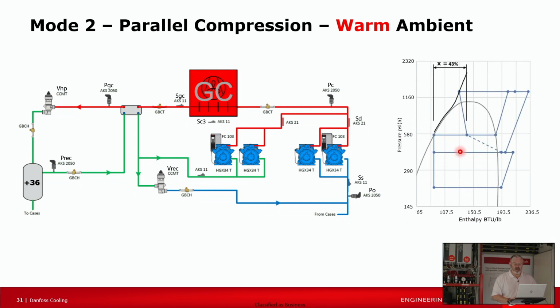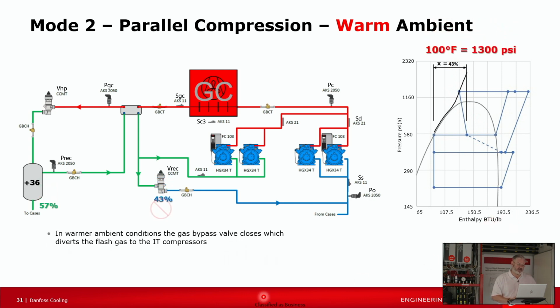So in a warm ambient, we've got 43% of our overall mass flow turning into flash gas that we can't use out at our cases to evaporate, absorb latent heat, and do work for us. That means 43% would be sent to the medium temp. That's bad because there's a better way. You purchased 2 compressors, pipe them in parallel. So we're going to close that receiver valve and force that load to now go up to your parallel compressors.